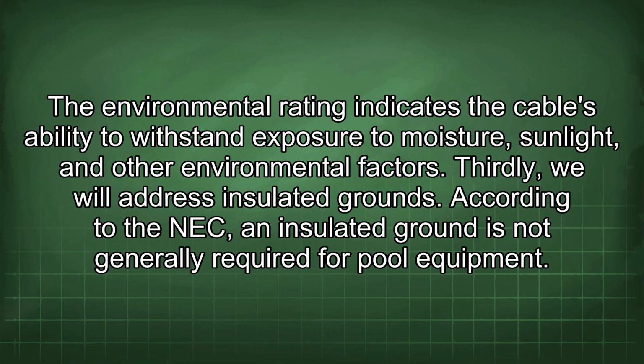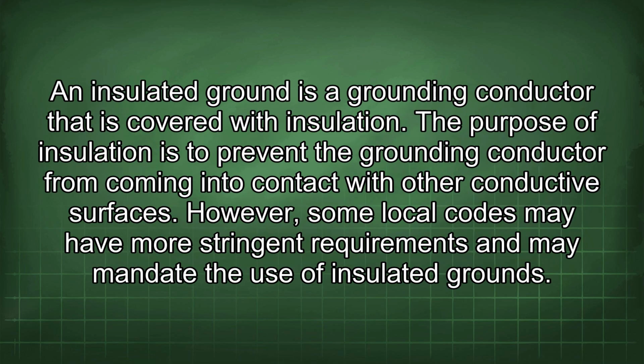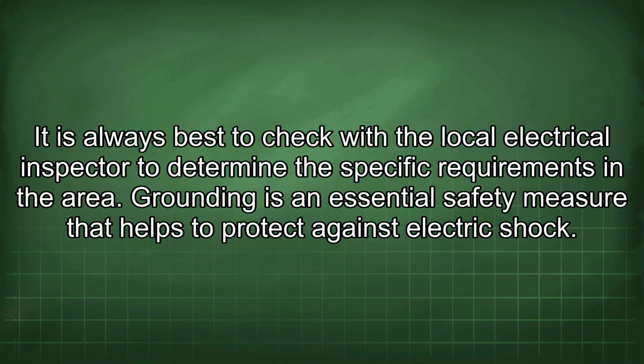Thirdly, we will address insulated grounds. According to the NEC, an insulated ground is not generally required for pool equipment. An insulated ground is a grounding conductor that is covered with insulation. The purpose of insulation is to prevent the grounding conductor from coming into contact with other conductive surfaces. However, some local codes may have more stringent requirements and may mandate the use of insulated grounds. It is always best to check with the local electrical inspector to determine the specific requirements in the area.